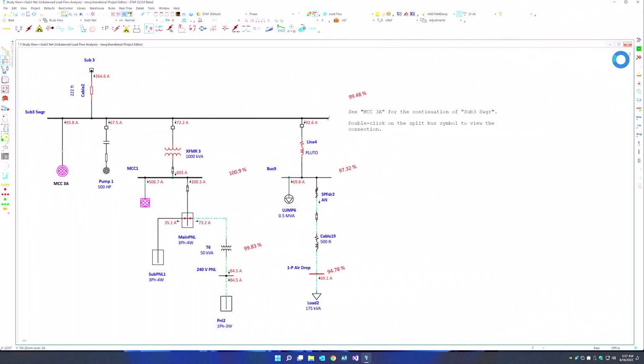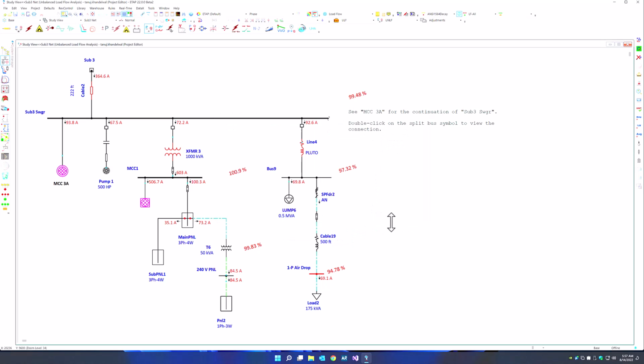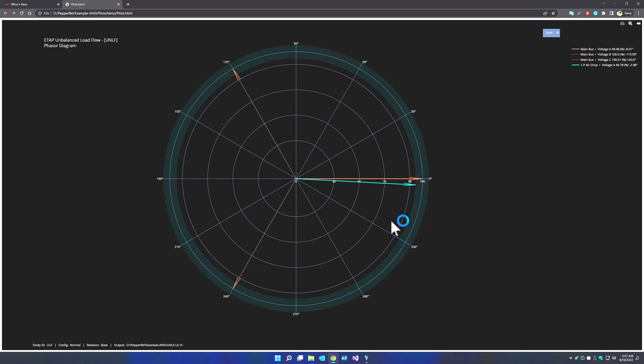We can go to the unbalanced load flow mode, run the simulation, go to our plot analyzer and pick a three-phase and single-phase bus. Look at the voltage phasors in a combination, and what ETAP gives us is a very clear indication or a clear picture showing us the phasors as expected for the main bus, which is relatively balanced, and our single-phase vector, which is magnitude and angle for the single-phase bus. And of course, with the plot analyzer, you can individually turn on or off any of these values, especially if you have a number of them plotted at the same time.